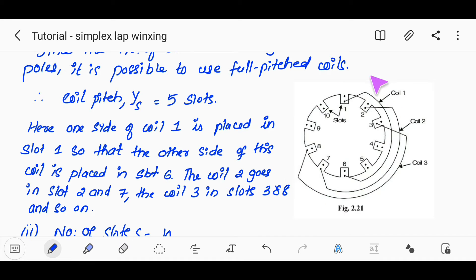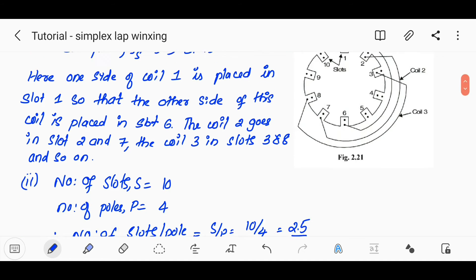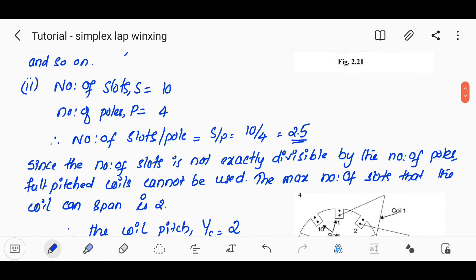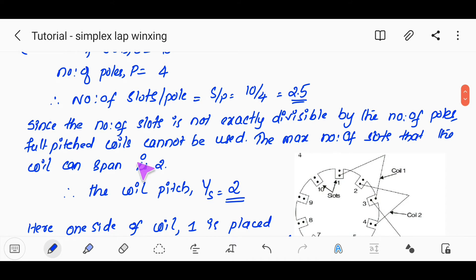We have the placement of the coils in each case. The number of slots S is 10 and number of poles P is 4, so slots per pole is S divided by P, which is 10 divided by 4, equal to 2.5. Since this is a fraction, the number of slots is not exactly divisible by the number of poles, so full-pitched coils cannot be used.